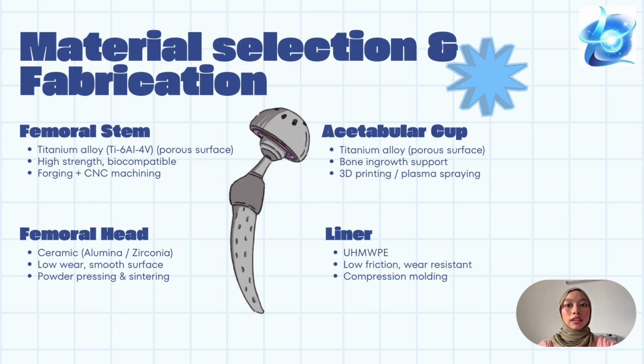The femoral head is made from ceramic material such as alumina or zirconia because it provides a very smooth surface and excellent wear resistance. The acetabular cup is also made from titanium alloy, often with a porous surface to promote bone ingrowth. The liner is made from UHMWPE, which has low friction and high wear resistance. Fabrication methods include forging and CNC machining for metals, sintering for ceramics, and compression molding for polymers.